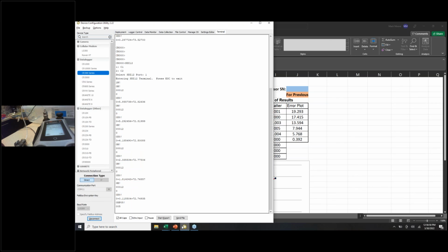Now it's in feet. So if I were to pump this up to, we'll put it 12, 11 or so feet, take another measurement. We were at 11.87 feet and it read 11.85 feet. So there we go. That's what's going on. It was just set for something other than feet. Once I set it back to feet, we can see we're pretty much right on the mark.